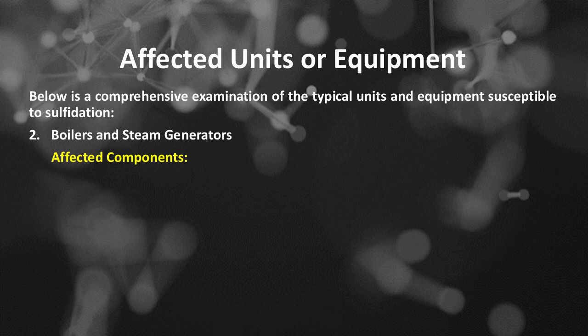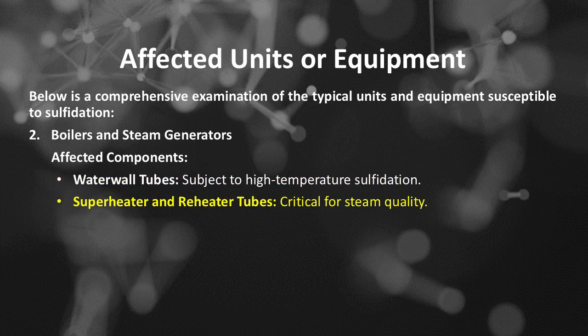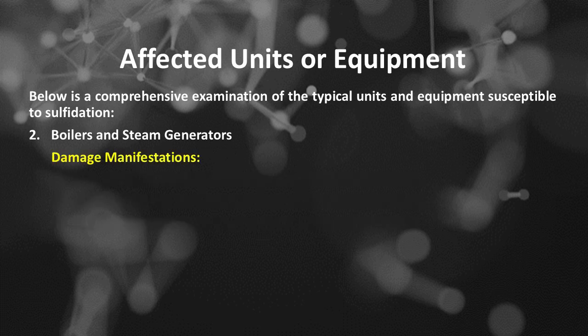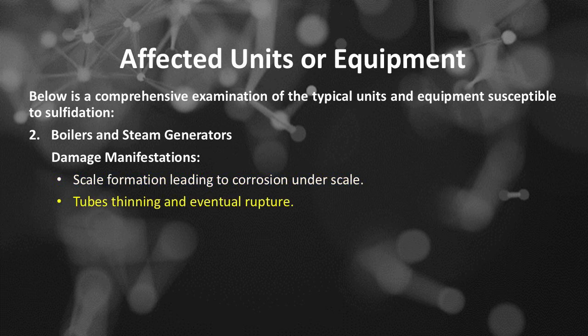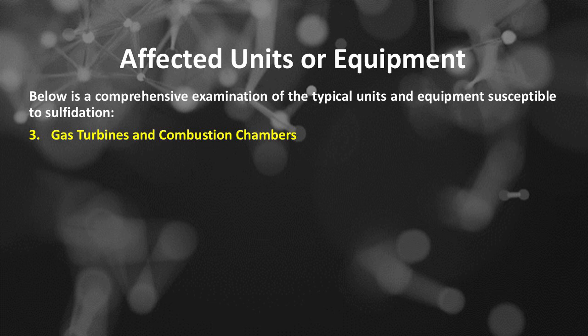Boilers and steam generators affected components. Water wall tubes, subject to high-temperature sulfidation. Superheater and reheater tubes, critical for steam quality. Furnace walls, exposed to sulfur-laden combustion gases. Boilers and steam generators damage manifestations. Scale formation leading to corrosion under scale. Tubes thinning and eventual rupture. Embrittlement causing cracking.